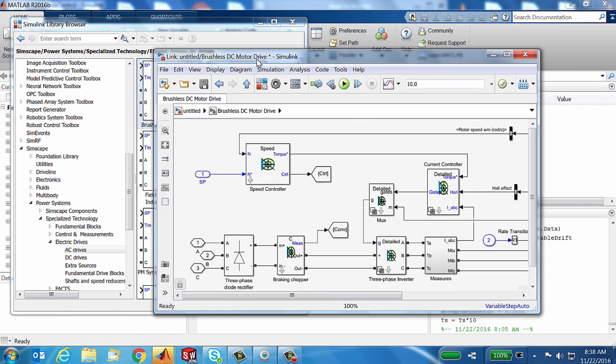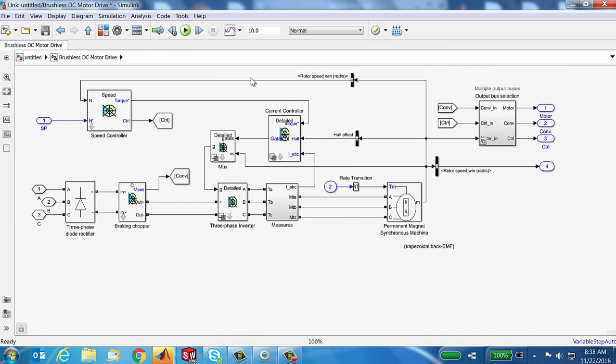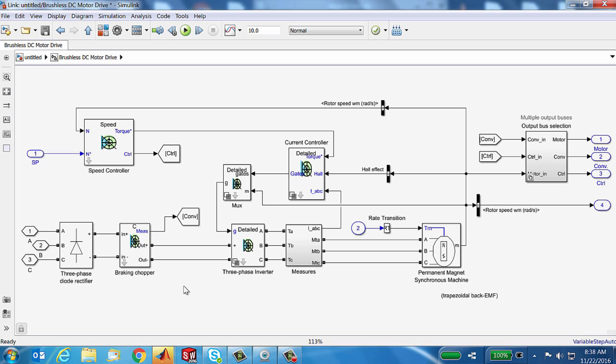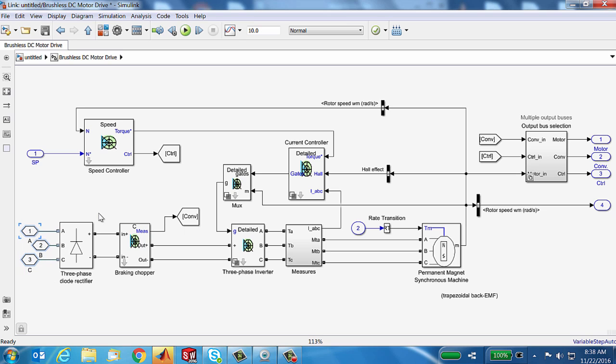We'll look under the mask. I'll begin by justifying why it's called a DC drive. You'll see one of the first things that occurs is that three phase AC source gets rectified to create a DC supply right there. That DC then gets presented to an inverter that ultimately puts the voltages that we want on the A, B, and C pins of a permanent magnet synchronous motor. And all this really takes place because of controls.